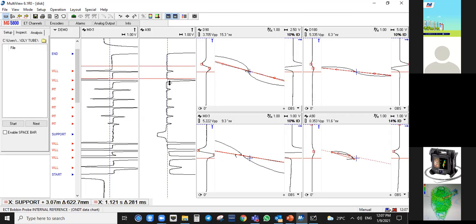Then you just analyze. Okay, for a typical inspection of tubes, inspectors usually only show the worst defect. For example, this is your first tube, and you see a lot of defects here, but the worst one is still the hole, right? So you go to the hole and put hole, and that's all. Okay, some clients want specifics: even though there are a lot of defects, you must show them. So it depends on the client that is asking you to do the inspection. But generally, the inspector just selects the worst one, and that's the one written on the report.